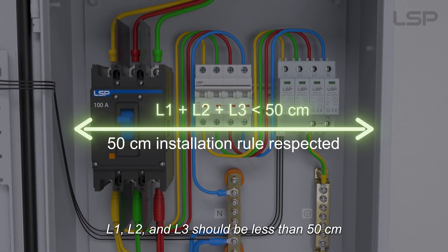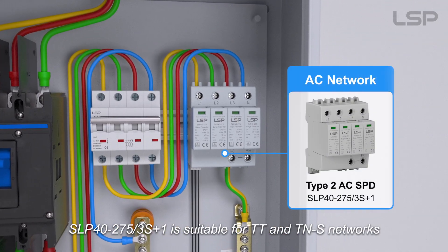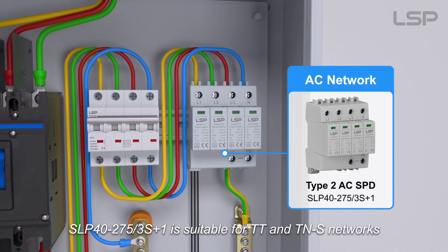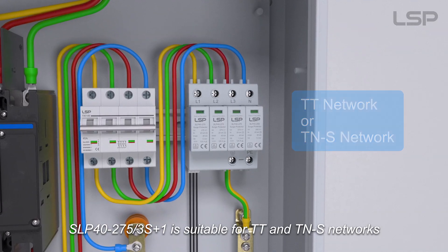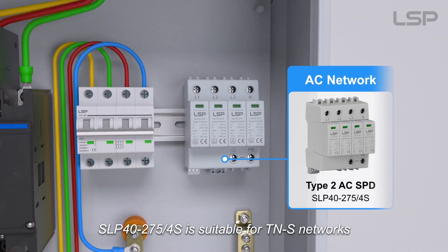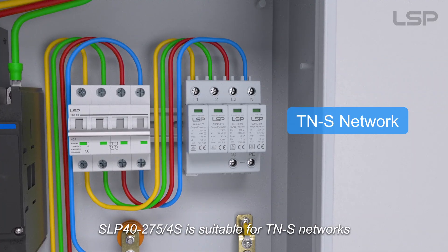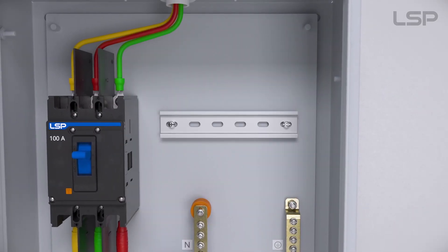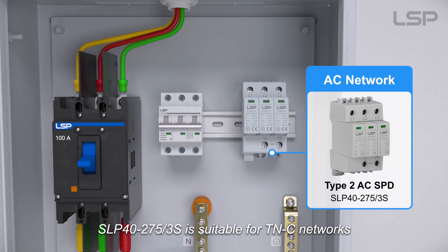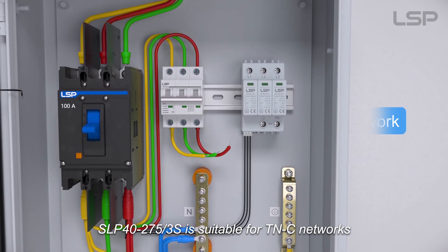The total length of the connections for L1, L2, and L3 should be less than 50 cm. SLP 40-275-3S+1 is suitable for TT and TNS networks. SLP 40-275-4S is suitable for TNS networks. SLP 40-275-3S is suitable for TNC networks.